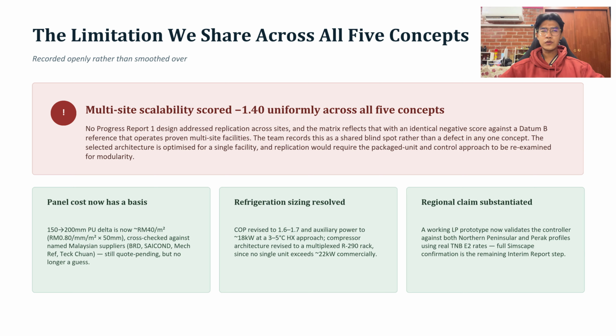Other things we used to flag as open are now closed. Our insulation cost has a real basis, about 40 ringgit Malaysia per square meter for the upgrade, checked against actual Malaysian suppliers, not just a guess. Hamid's refrigeration sizing is fully worked out with real numbers, and Robbie's has 2 real region tested results now using actual electricity tariff rates, not just a plan to test it later.